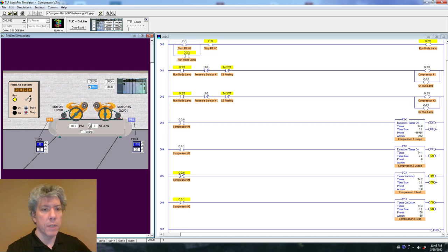So let's give it some outflow. Let's dump some of the pressure in the tank. And to make our lives quicker, we'll go down to 10 PSI. And so down at 30 PSI, it should start running. There we go. So now let's take the outflow down to 0%.